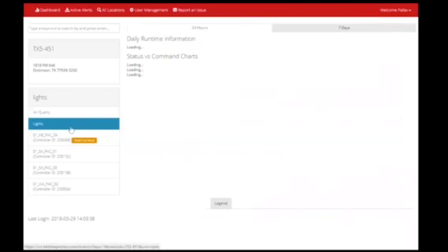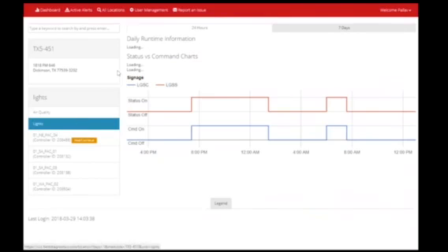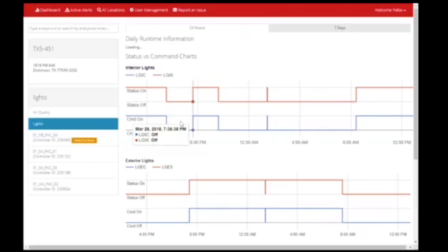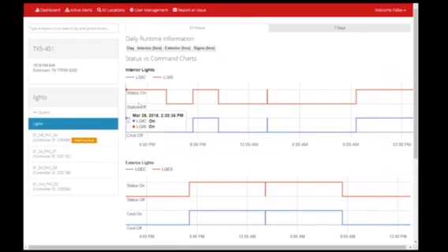So similarly, you can go into lighting views. And again, the system understands how industrial IoT works. So you can see there is the concept of a command and a status, because as you're working with these distributed systems, you can send a command and you're not really guaranteed that the status actually took. Something broken on the equipment could cause the status not to change. So there's two charts that we look at together, and if they're not matching up, that's one type of error that can happen.